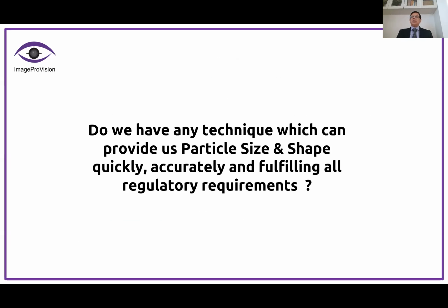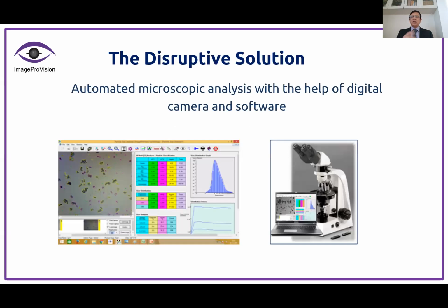So these are the challenges thrown by US FDA or any FDA on particle analysis. Do we have any technique which can provide particle size and shape quickly, accurately, and most importantly, fulfilling all regulatory requirements? As I told you, I'm going to talk about the system. It is a microscopic based particle analysis system, which has a motorized XYZ stage, a digital camera, and a patented algorithm, which does the analysis part.